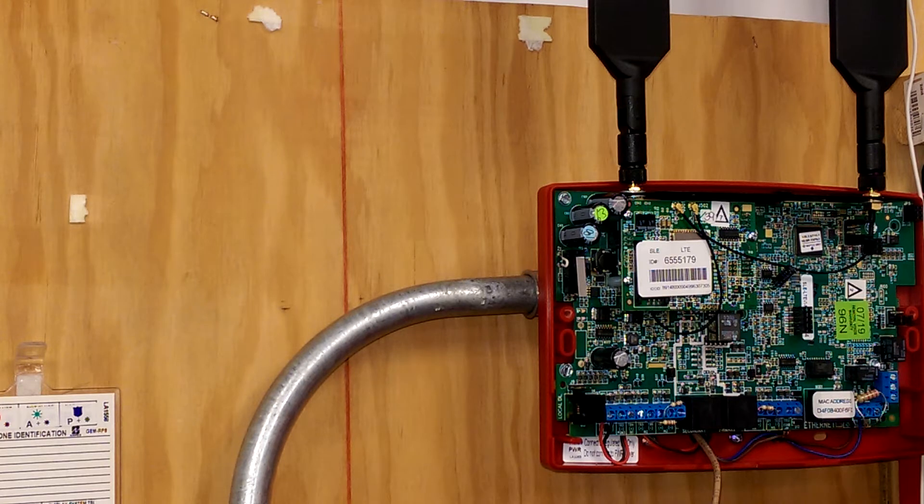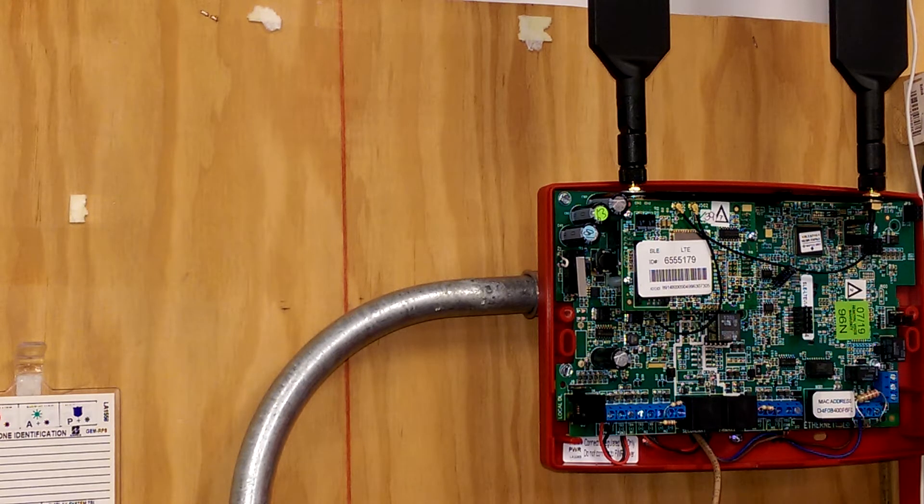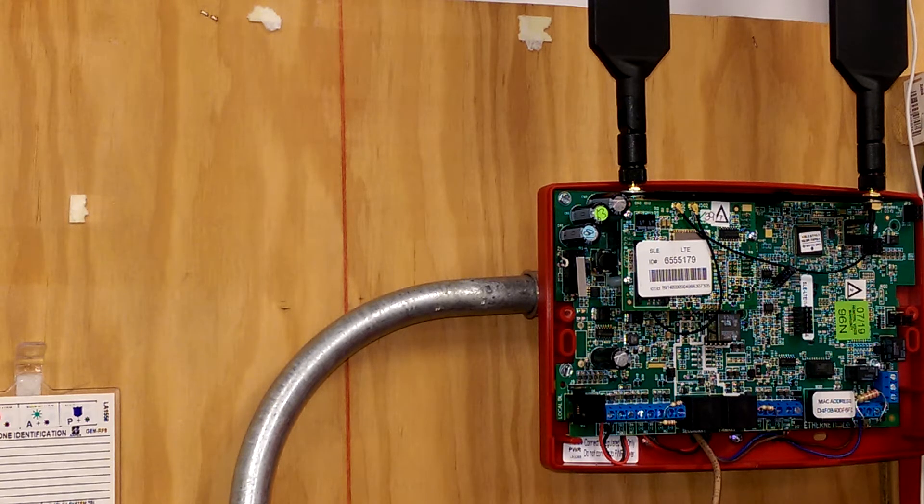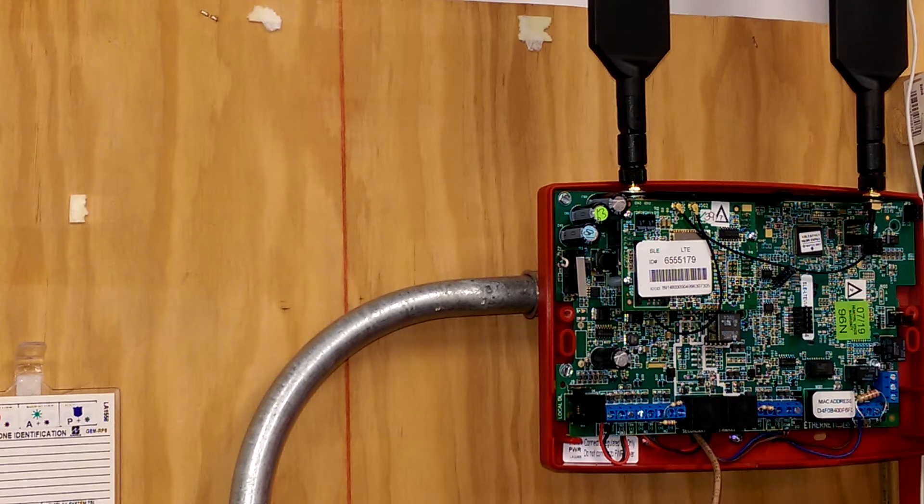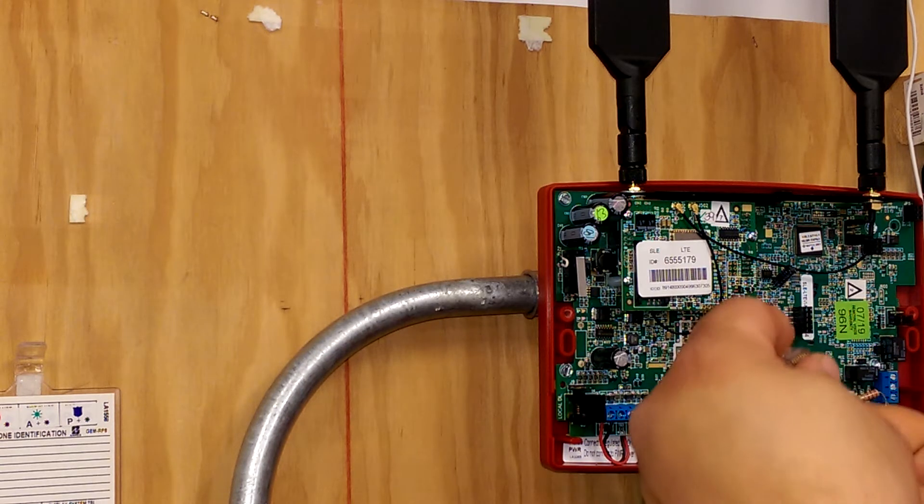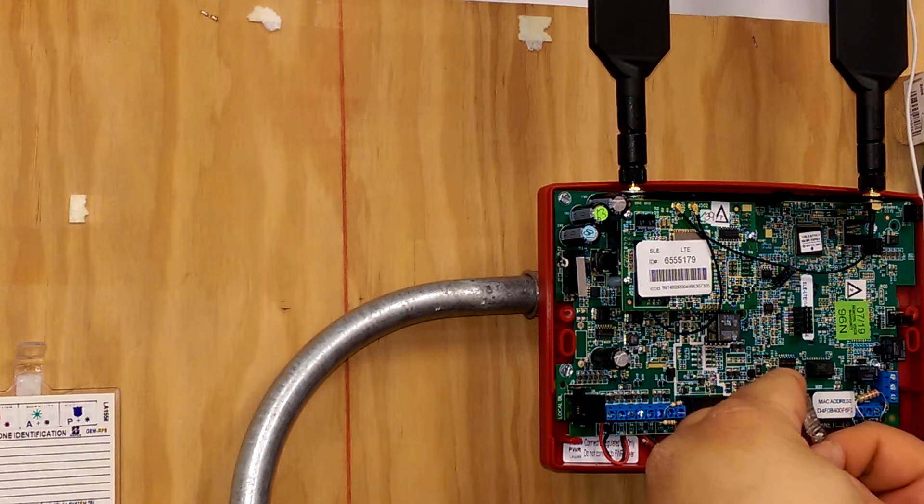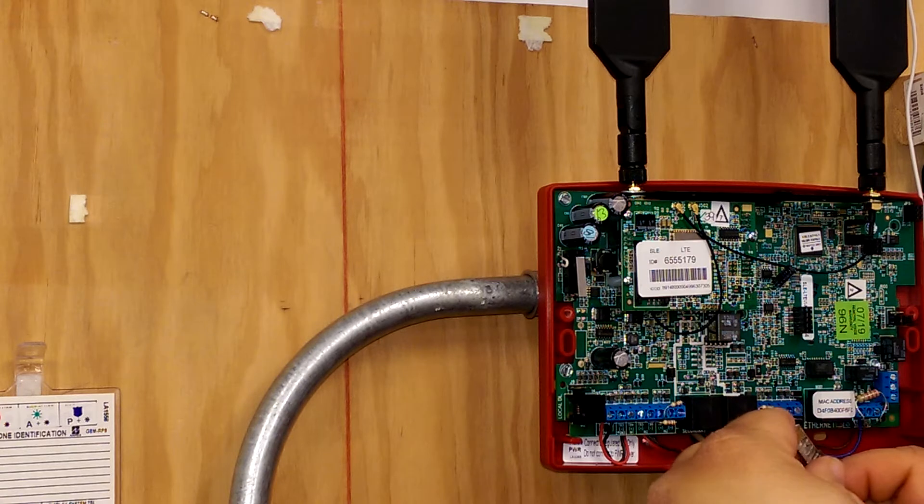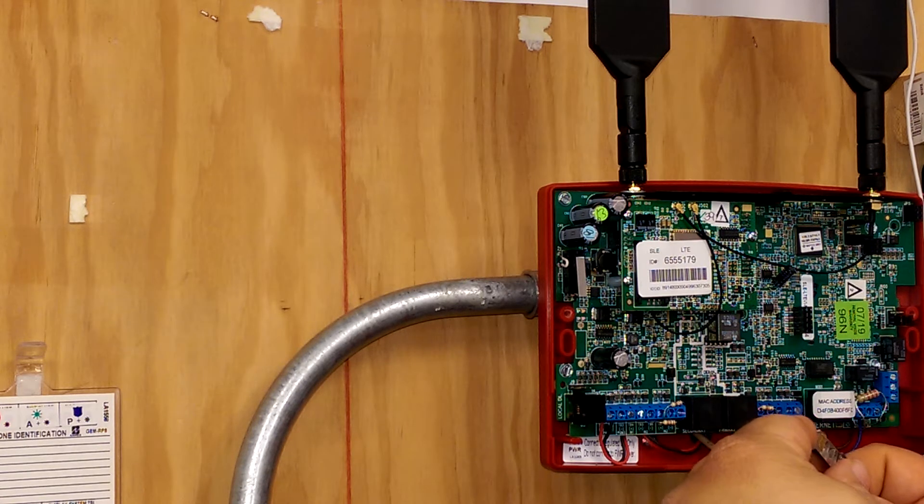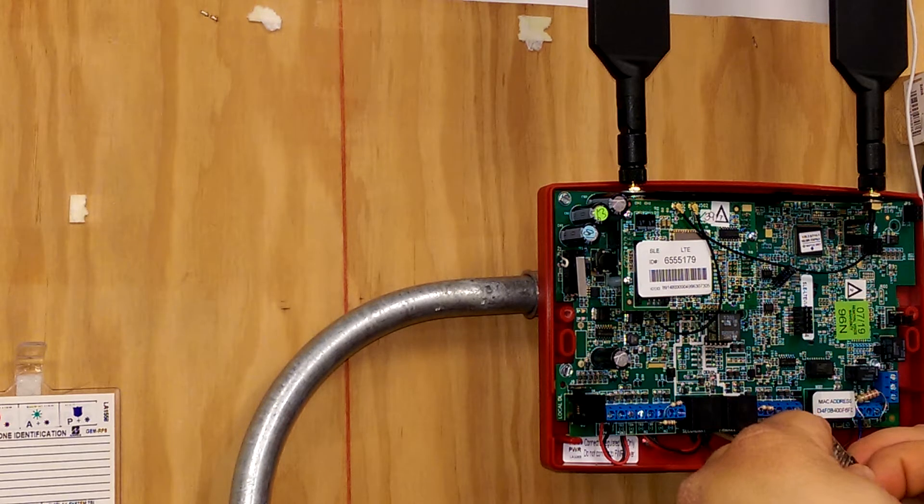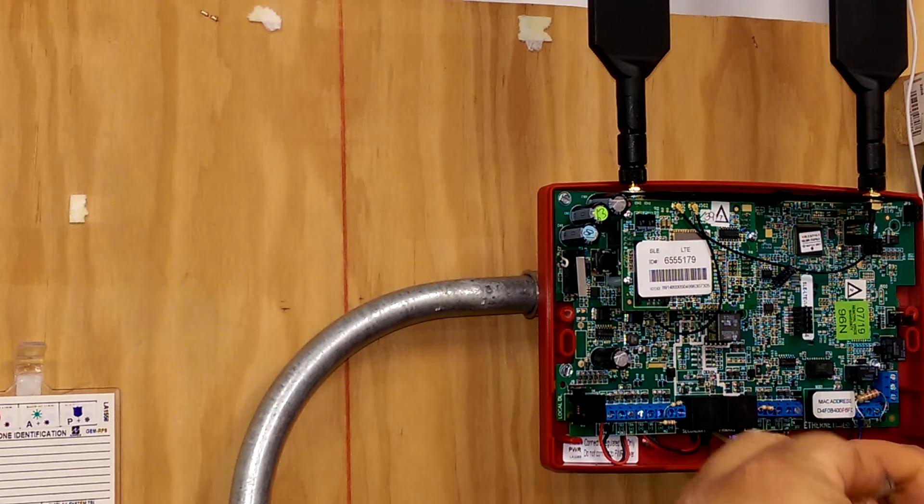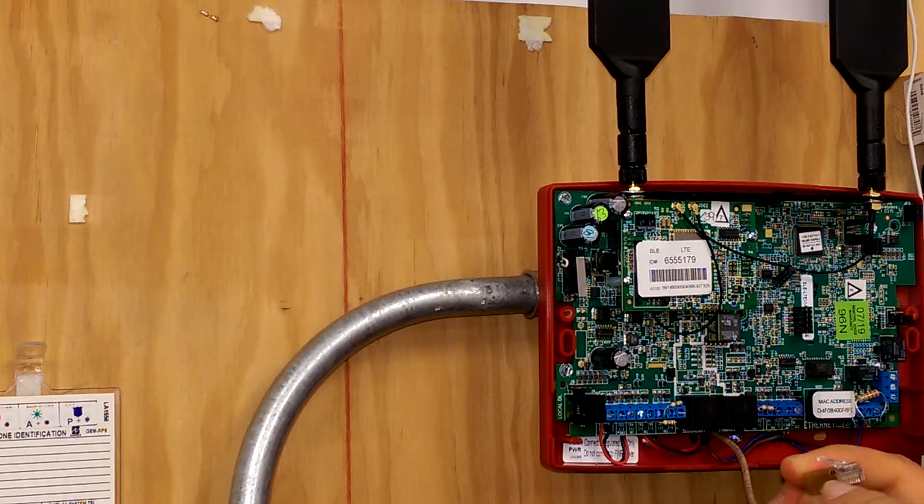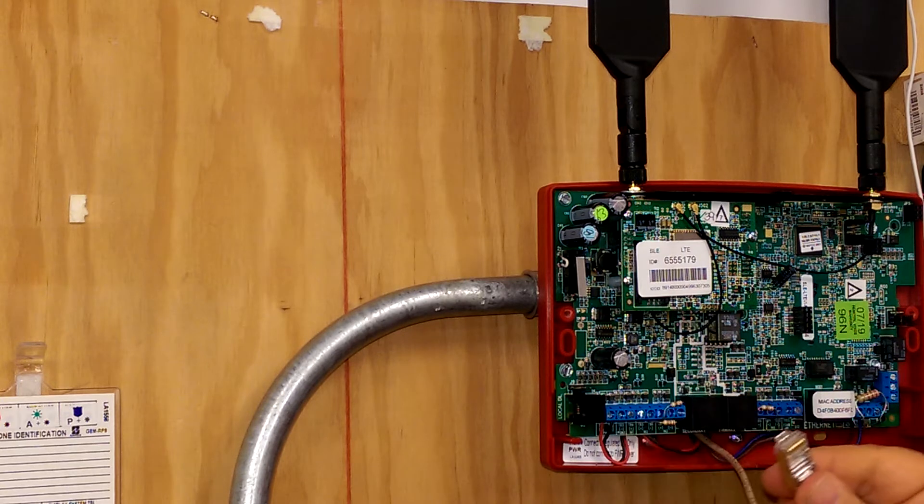And finally, this radio has modular plugs to connect to the fire alarm control panel. So we may need to do a crimp. This is pretty simple. Just one 22-4 wire will suffice because we just need tip and ring, the center two pairs. So we can just take a modular jack and slide it on, making sure that we are in the center two pins. You should have three empty pins on each side.